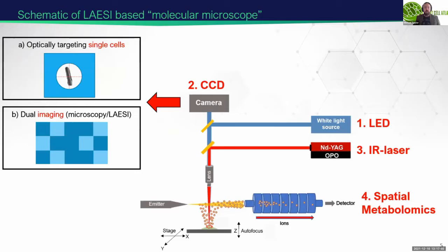This is a schematic of the LAESI-based molecular microscope we've been designing. Very simply, we have a sample stage where we place the cell-containing samples with an LED which illuminates the sample surface. Then we can take an image using the camera at the top of the optical stack, identify where cells are, and fire the laser at each cell sequentially, collecting spectra and therefore a metabolic profile. That's the first mode. The second mode is we can perform dual microscopy and LAESI imaging of the sample.